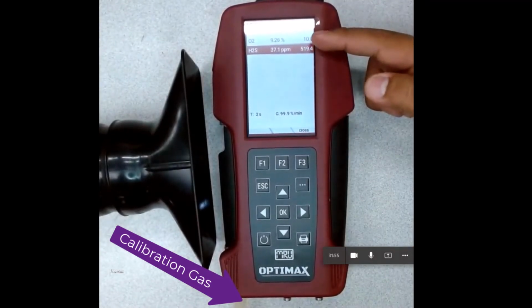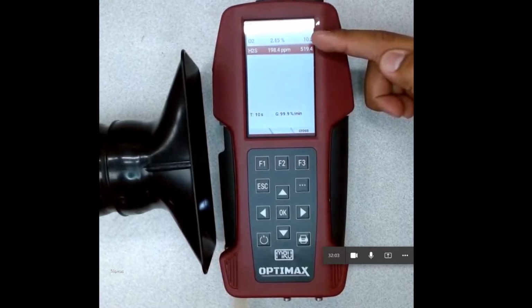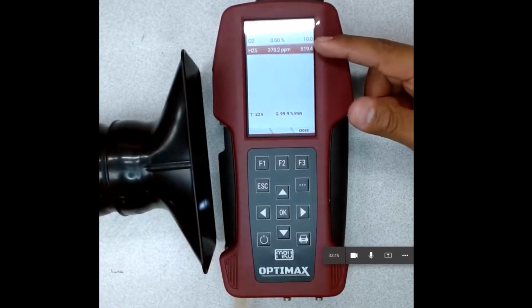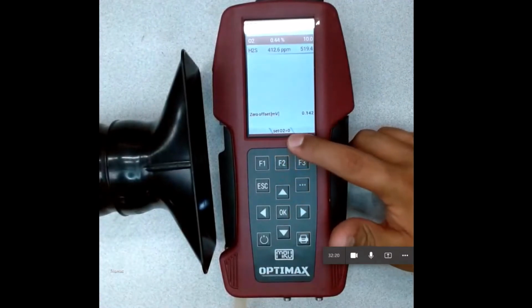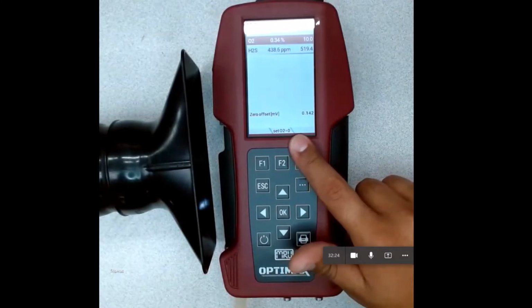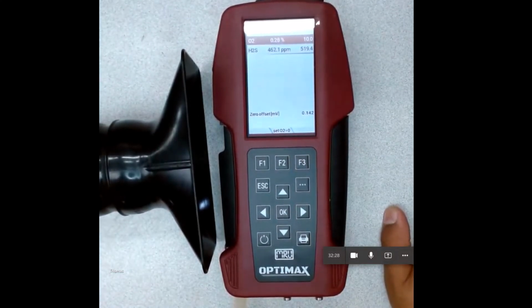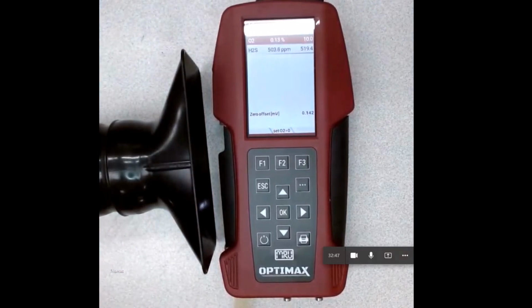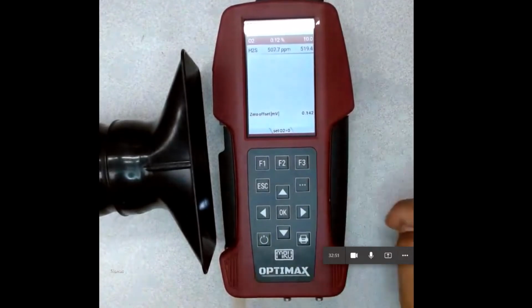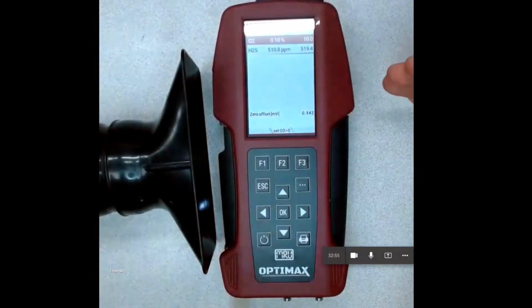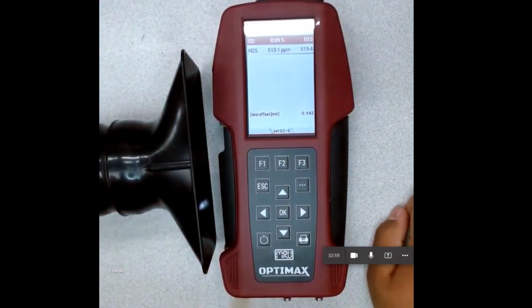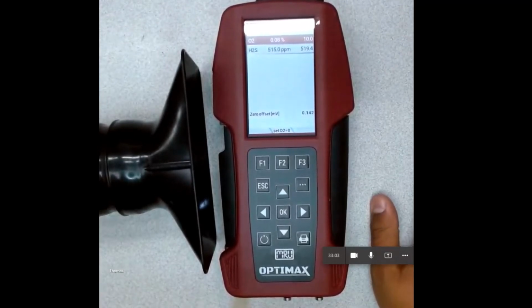you'll see the oxygen value start to come down. And right when it starts getting around 1%, once it gets under 1%, and then it starts to become stable, you'll see this option pop up right here. You see set O2 to 0. Yeah, so that's why we don't need to change the 10% because it opens up this option whenever the O2 percentage has come low enough. So it safeguards itself from an improper 0 gas.